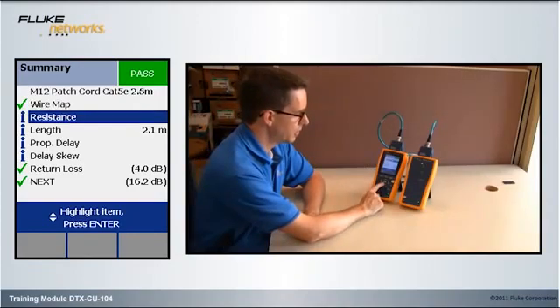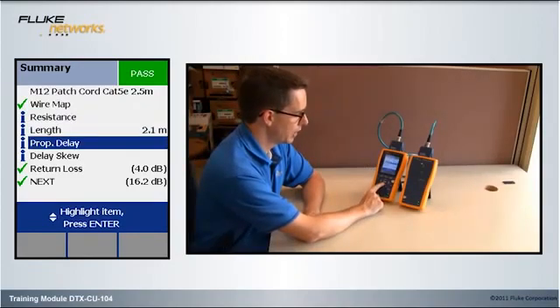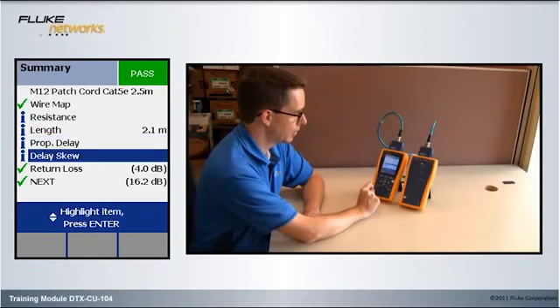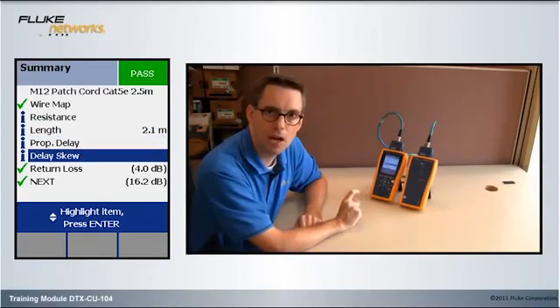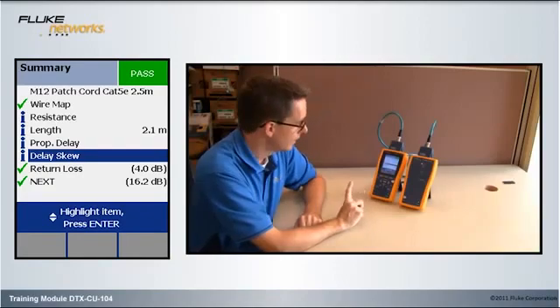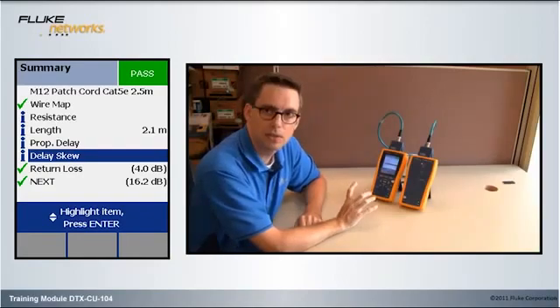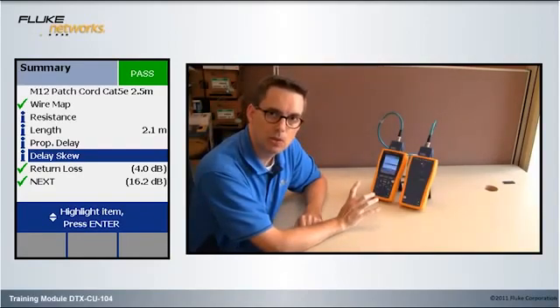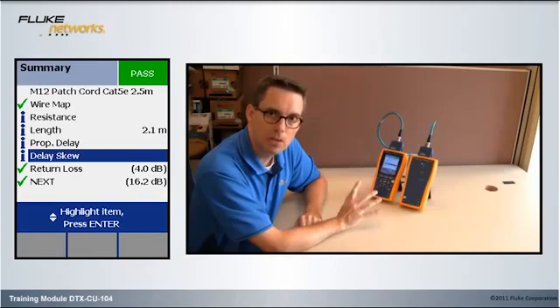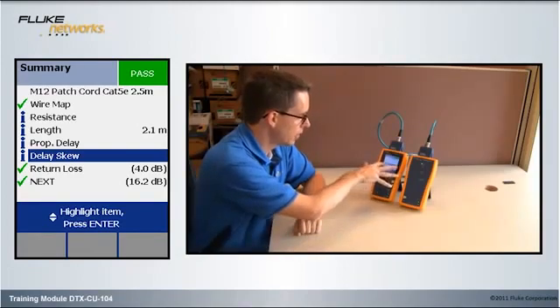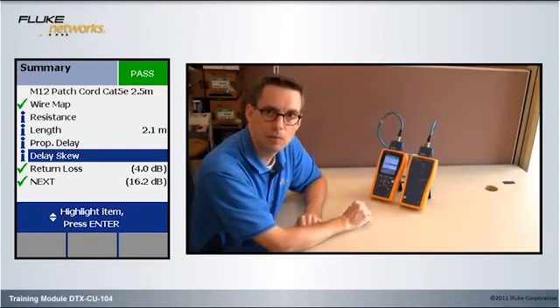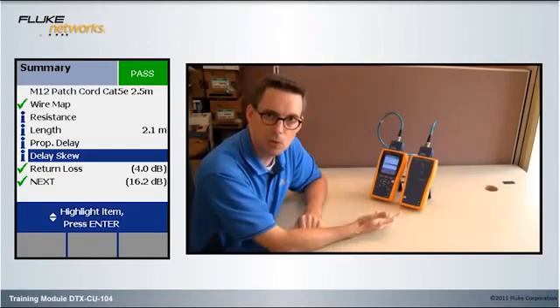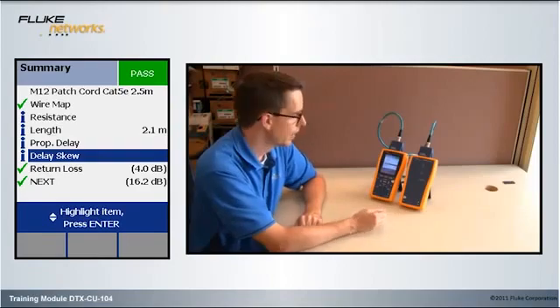Now, you'll notice that with resistance, length, propagation delay, and delay skew, they have the letter I next to them. That means information only. That's because when you're doing patch cord certification, there is no limit for resistance, length, propagation delay, and delay skew. But customers want to know those values, so we actually make the measurement and record them.